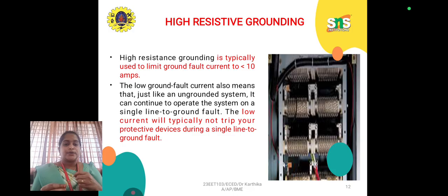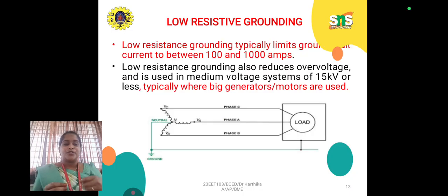Here, which is the low current, it will typically not trip your protective devices during a single line to ground fault. This low ground fault current also means that, just like an ungrounded system, it can continue to operate the system on a single line to ground fault. That's it. Okay, and low resistive grounding, here it limits the current between 100 to 1000 amps. It is typically used in big generators or motors.